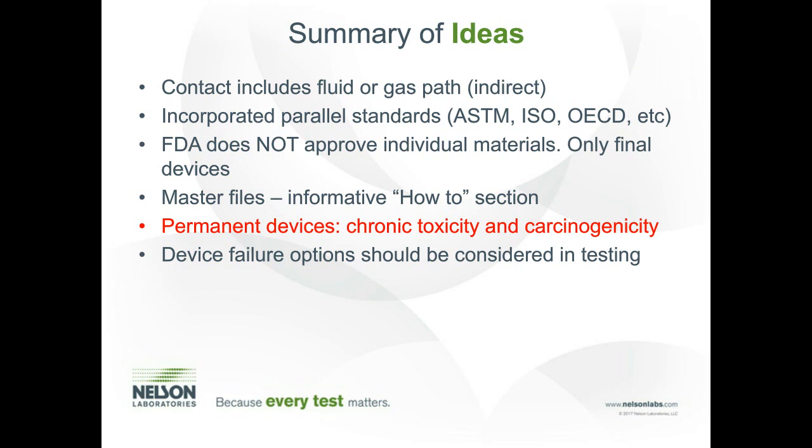And that includes chronic toxicity and carcinogenicity. So if your device has one of those endpoints, you can no longer submit without some kind of justification around those two endpoints. That can be a material assessment if you have good information about the processing and materials, but a lot of the time what we recommend is the extractables and leachables.